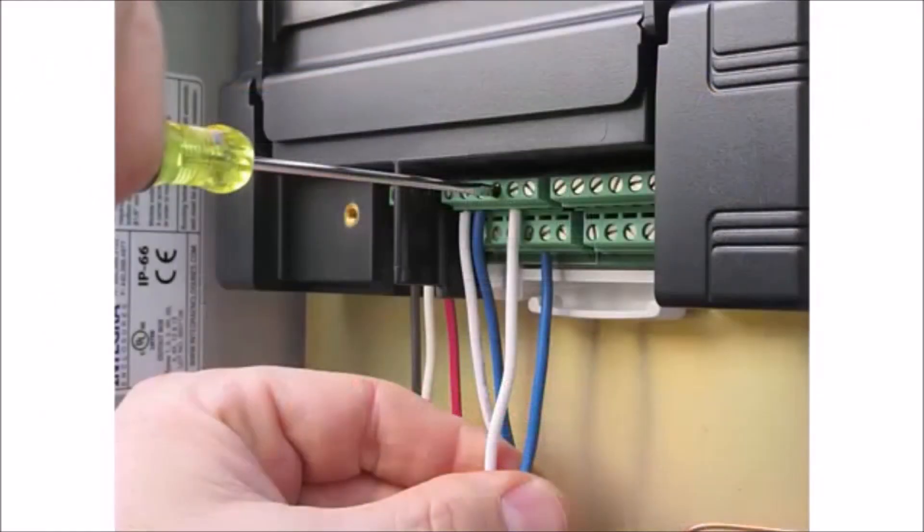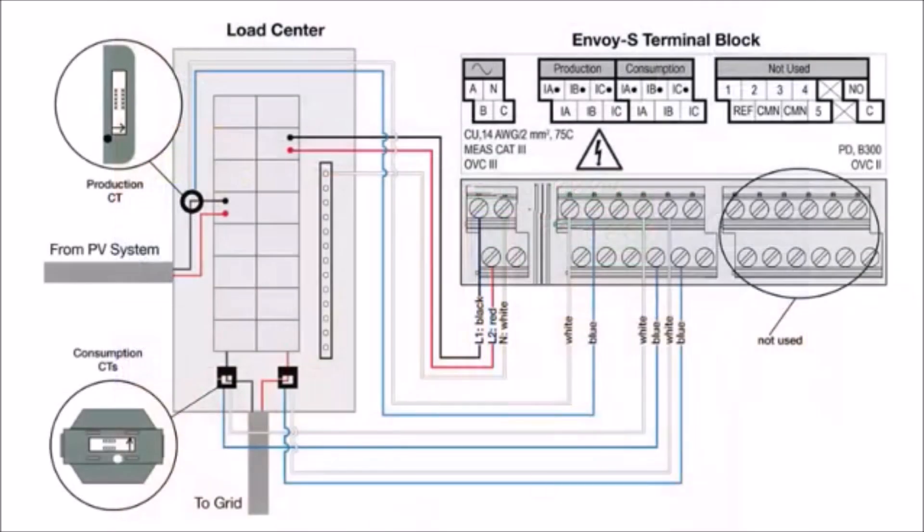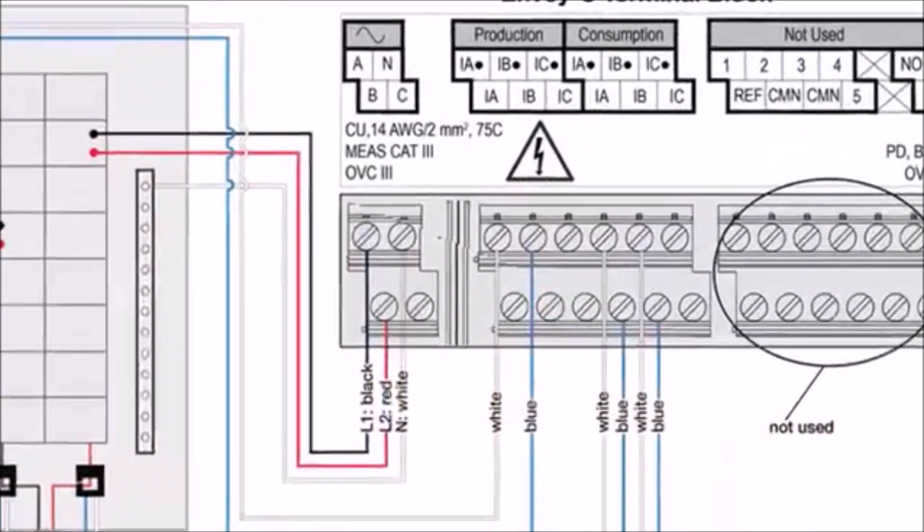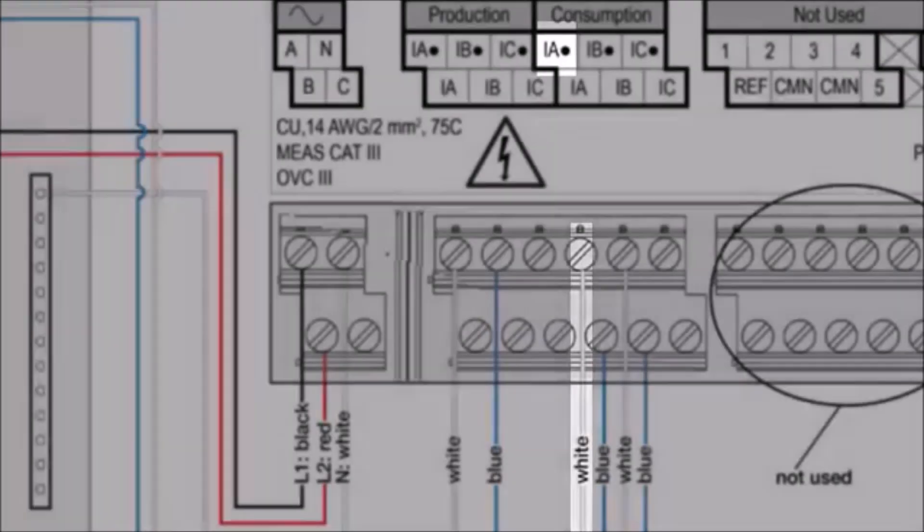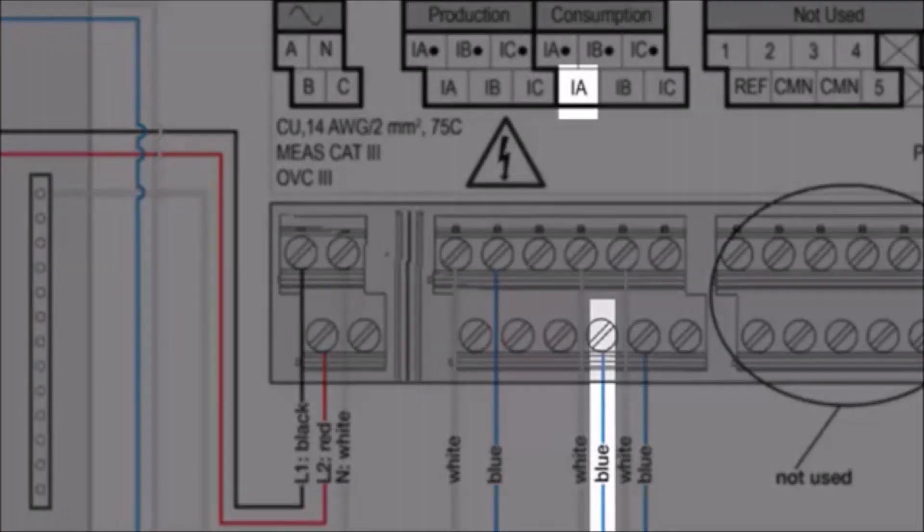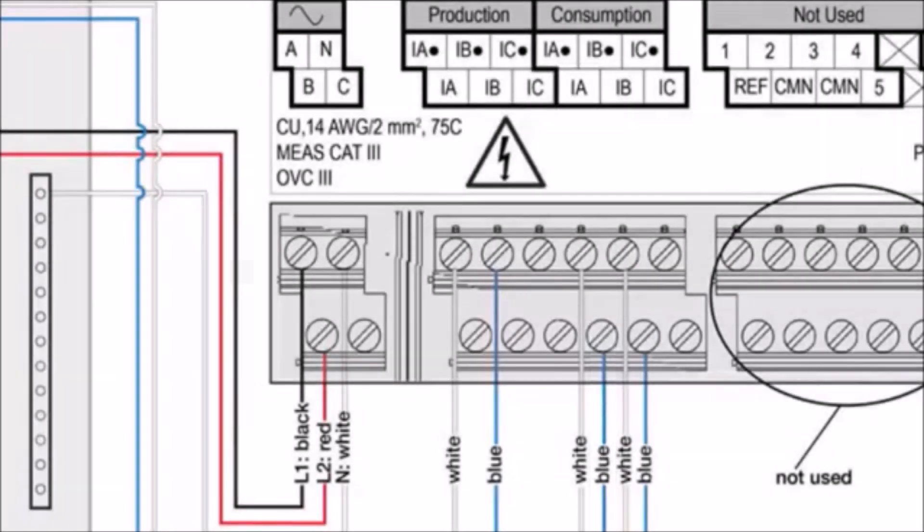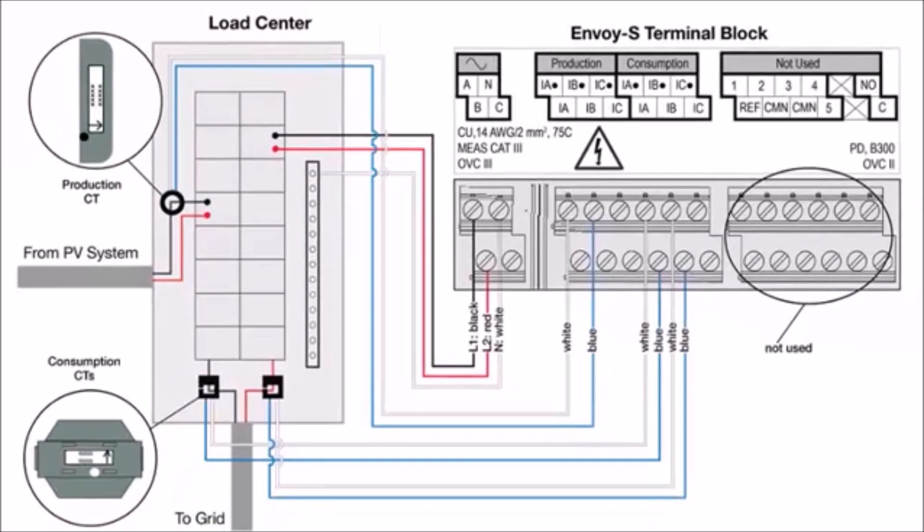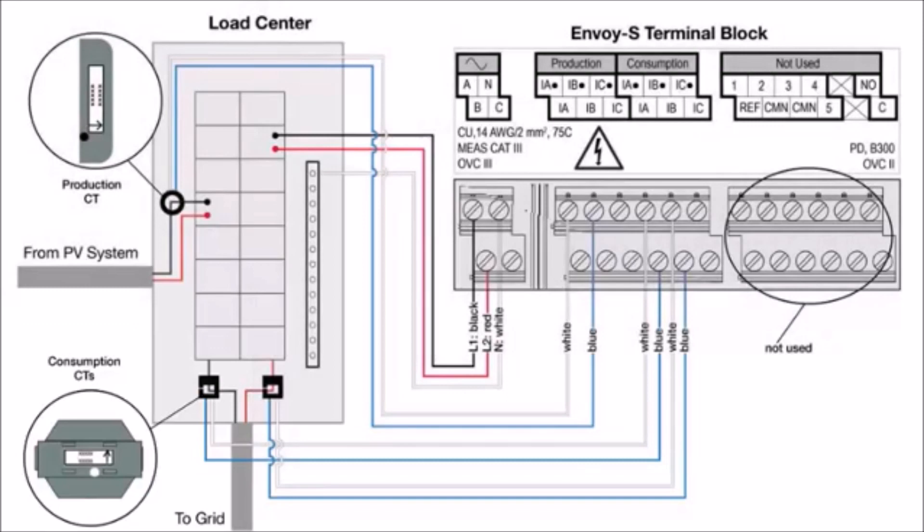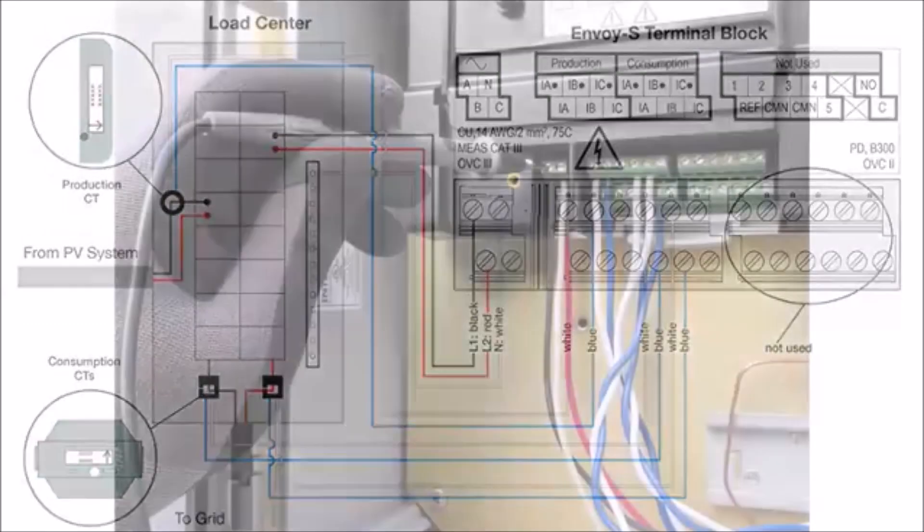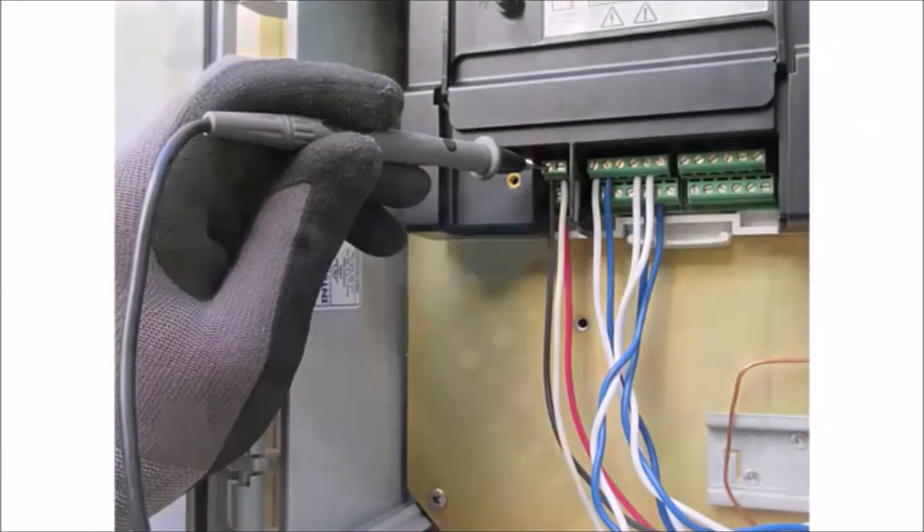Connect the CT wires to the Envoy before clamping the CTs onto the main service conductors. For the marked CT wires, connect the white wire to the line 1 I-A dot terminal and the blue wire to the line 1 I-A terminal. Note that the line 1 consumption CT installed on terminal I-A must be attached to the same line as the power terminal A of the Envoy-S. This can be verified with a voltmeter.